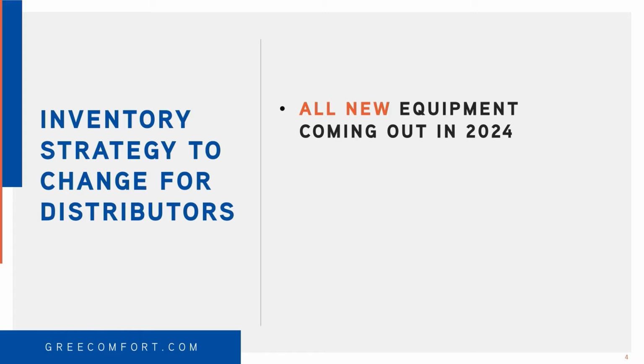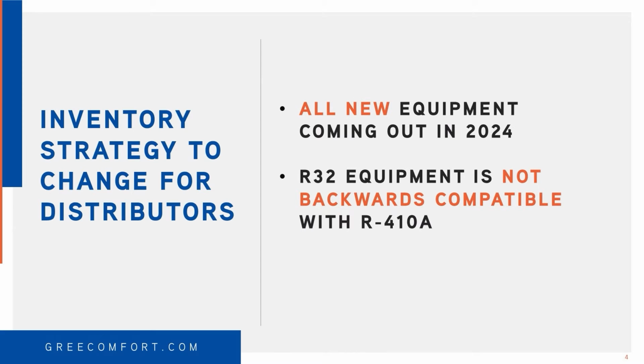And we also have to note that all of the R32 equipment coming out is not backwards compatible to the old 410A equipment. It's new refrigerant, new compressors, and because of the safety requirements, you can't take an R410A ductless head and put it on an R32 outdoor unit. It won't work and it's unsafe.